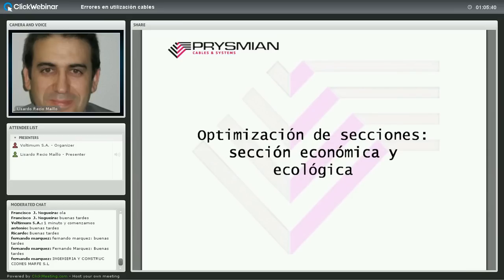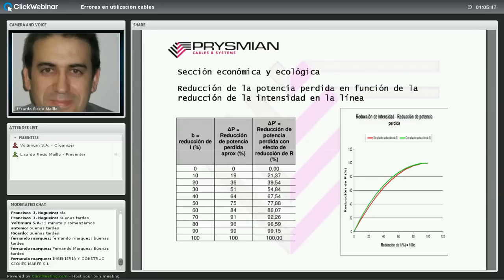Segundo punto: optimización de secciones, sección económica y ecológica. Se trata de aumentar la sección del cable —con lo cual el cable será más caro— pero a su vez se aminoran las pérdidas por efecto Joule en la línea. Toda corriente que circula por un conductor genera calor que pasa por el contador y hay que pagarlo. Si aminoro esas pérdidas caloríficas aumentando la sección, pasará menos energía por el contador. Ese es el concepto de sección económica.